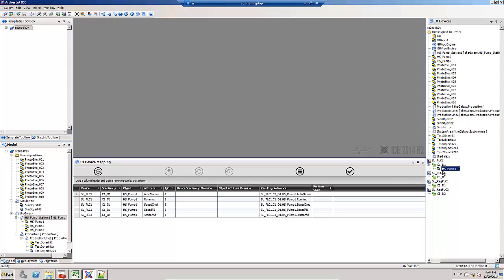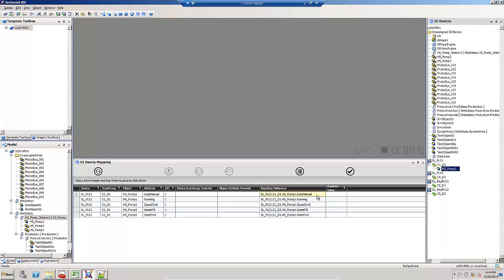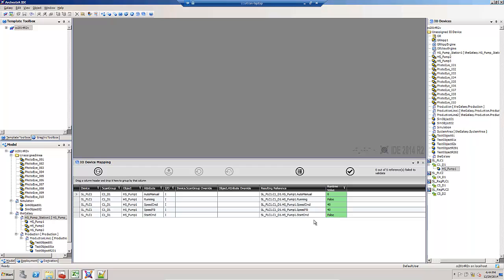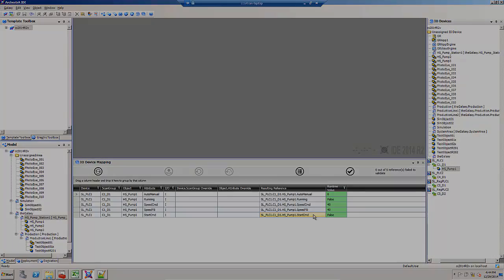Click and drag to assign it to this particular topic. Notice now when I highlight, my fault attribute doesn't show up in the list because I have not configured it to be auto mapped. I can still validate these and they will validate fine. Because I've hard coded the reference in the fault, it won't show up in the I.O. mapping.